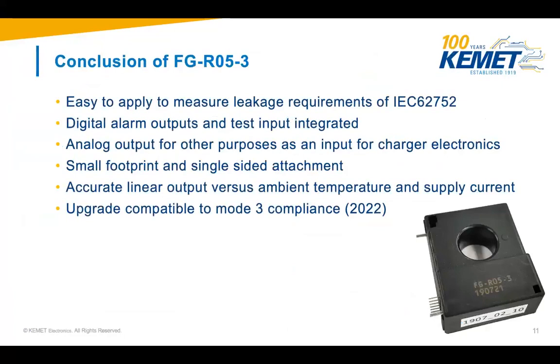So, the conclusion: the FG-R05-3 is easy to apply to measure the leakage requirements of this Mode 2. It has digital alarm outputs, an integrated test input, and an analog output for other purposes, whatever you need in the charging electronics, and a small footprint. This is of course one of the major benefits, along with single-side attachment.